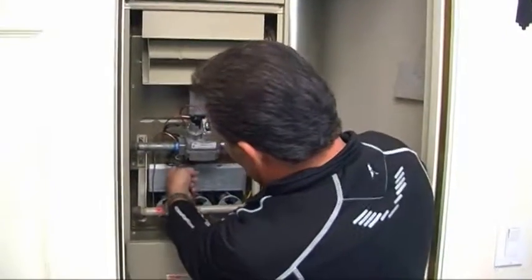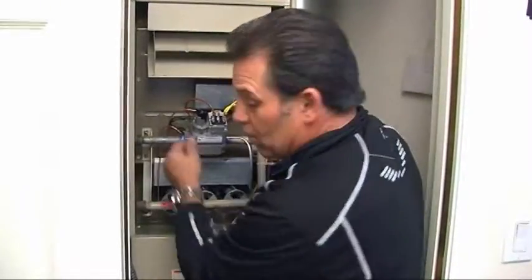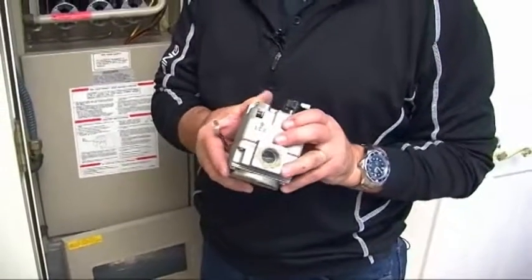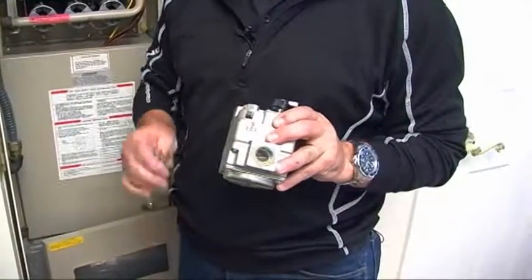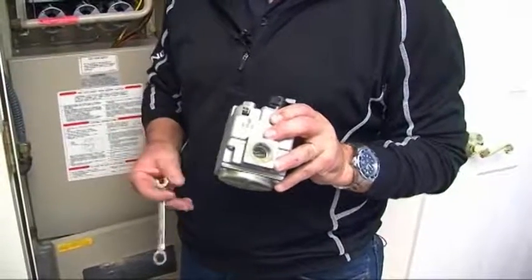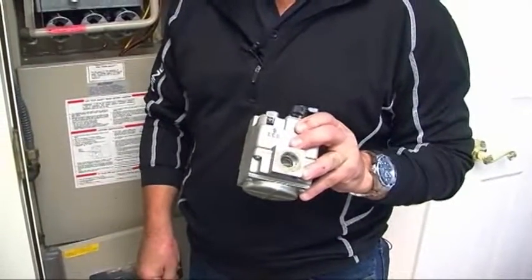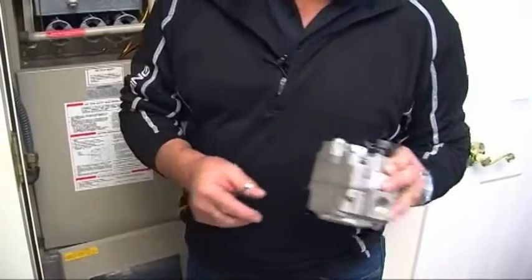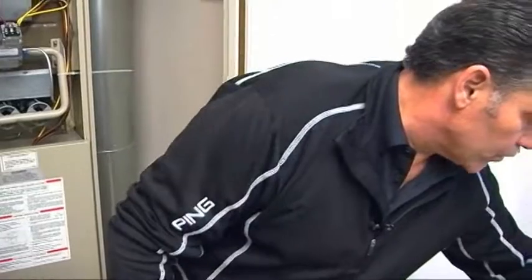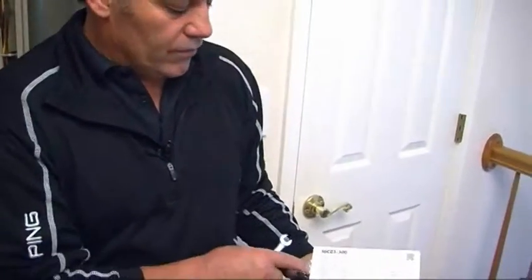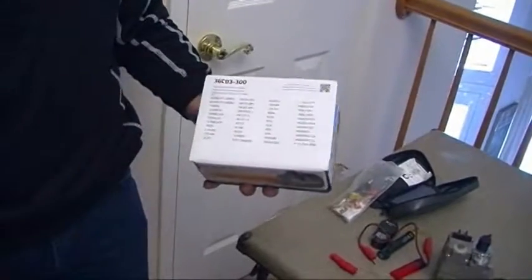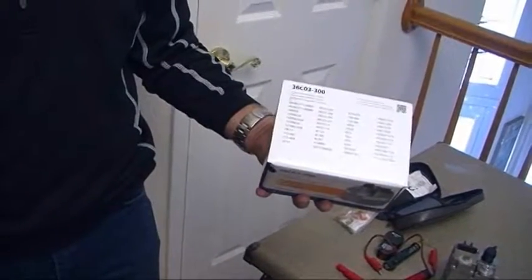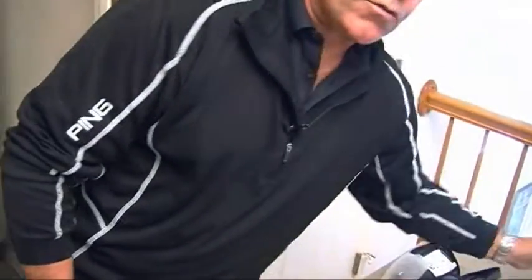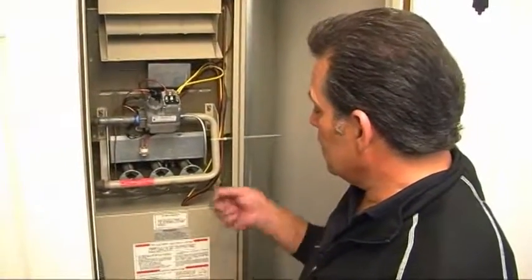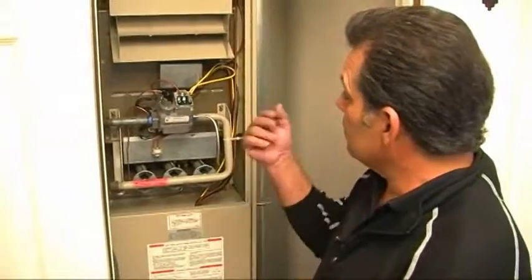The last thing that we have is an over temperature switch in the heat exchanger, which is these black wires that go to the ECO, which is the energy cutout. On this gas valve and on this furnace, they have an energy cutout. So if you ever do come across those, you must connect them up or jump them in order to get the furnace to turn on. This is a universal gas valve that we're putting in, and it replaces all of these different gas valves. It's a universal standing pilot gas valve that can also be used for millivolt. So now I'm going to go ahead and relight the pilot, plug it in, and let it kick back on.